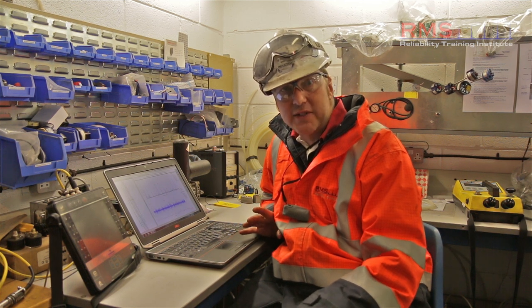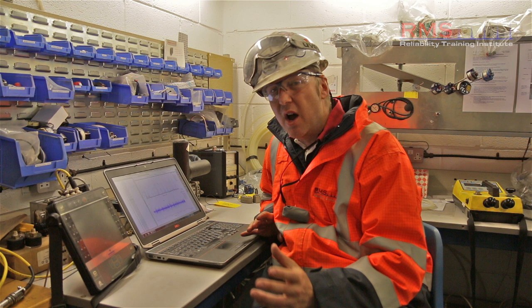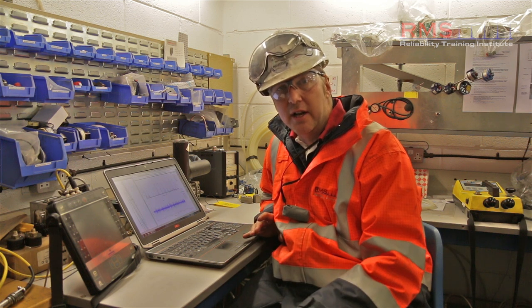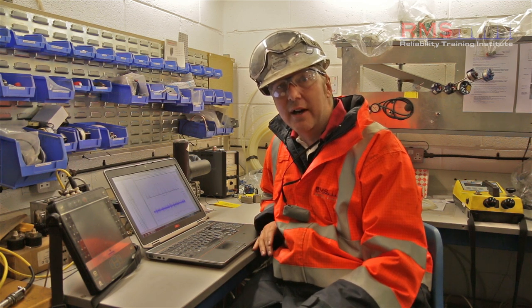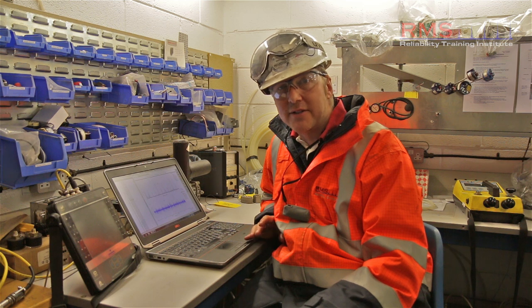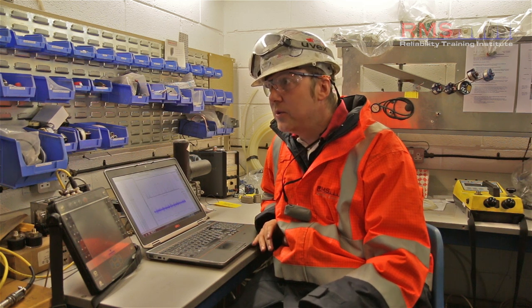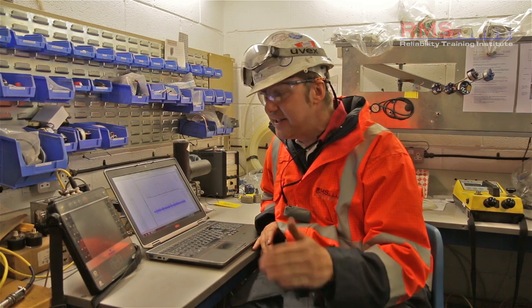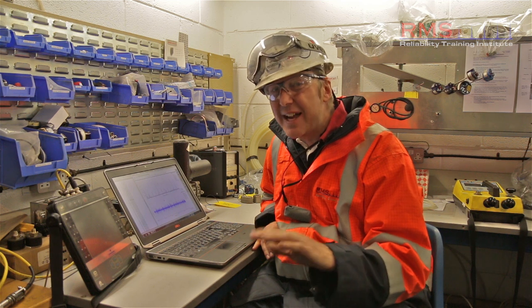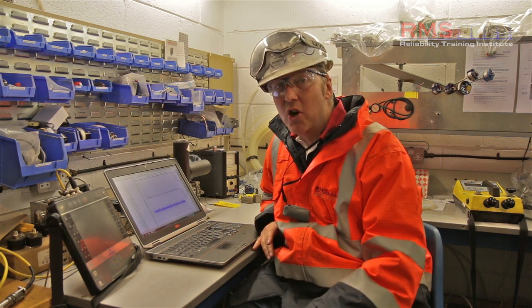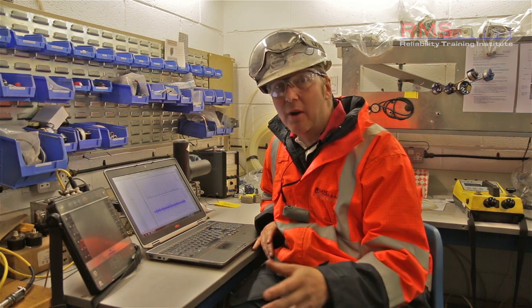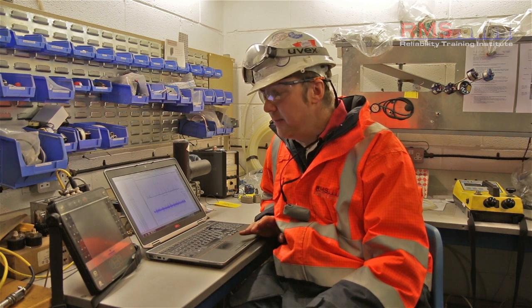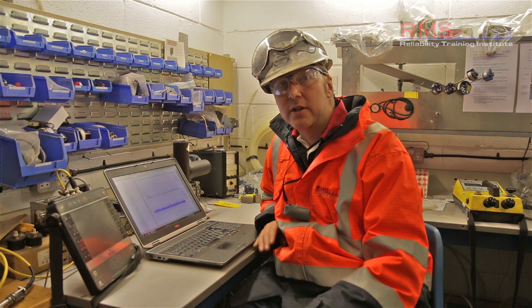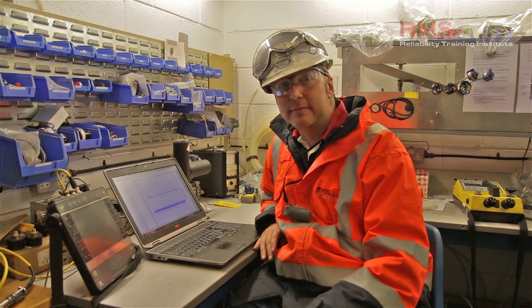We'll get them to change both sets of bearings on the fan, even though we know it's just the drive end bearing. It'd be good practice to do that. And that's it, really. The only thing you've got to watch out for, if the data starts to hump up, and the levels actually start to drop, that's not a good sign, and the harmonics start to drop, then I'll start to get worried. But for the minute, I think we're going to make that shut. So let's keep an eye on it and take it from there.